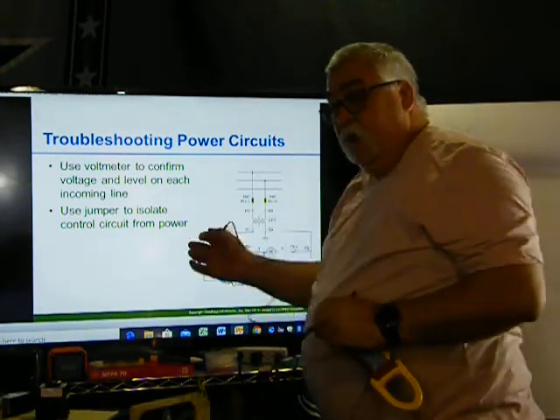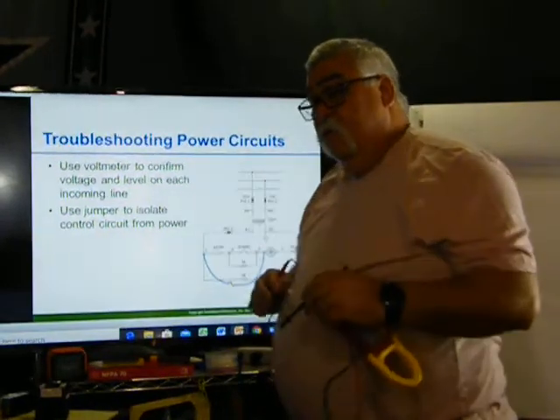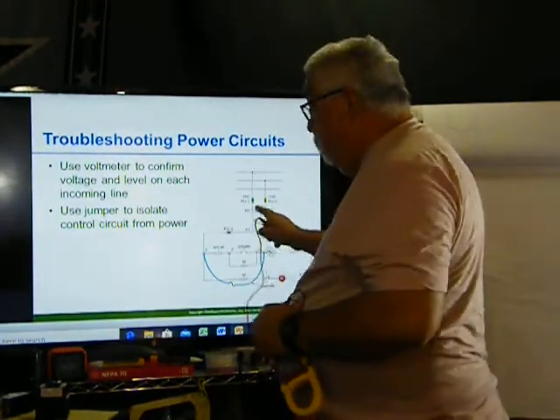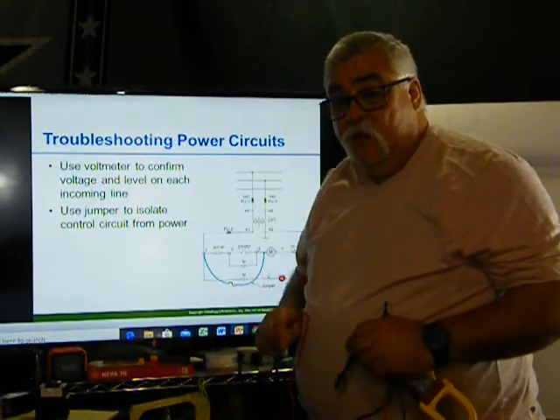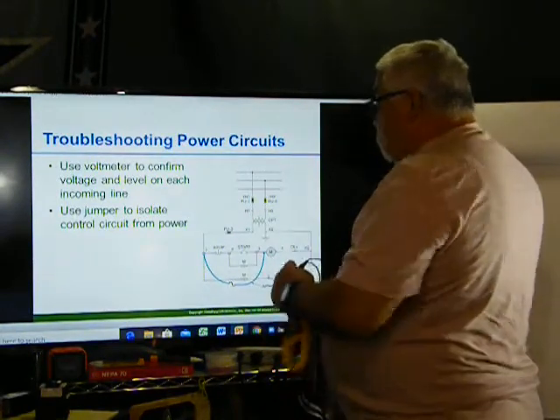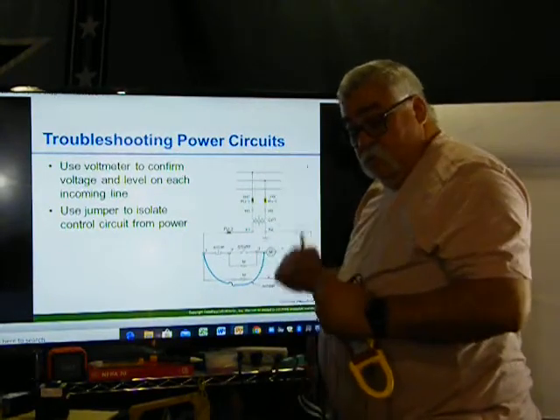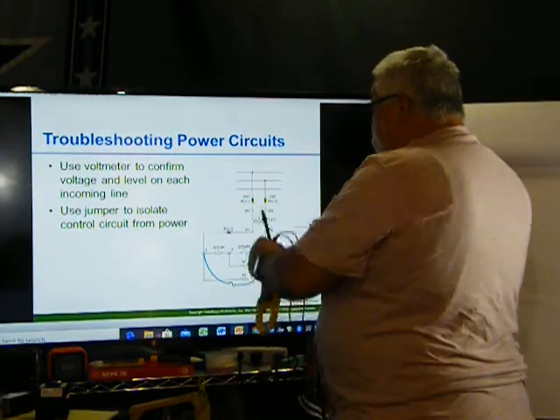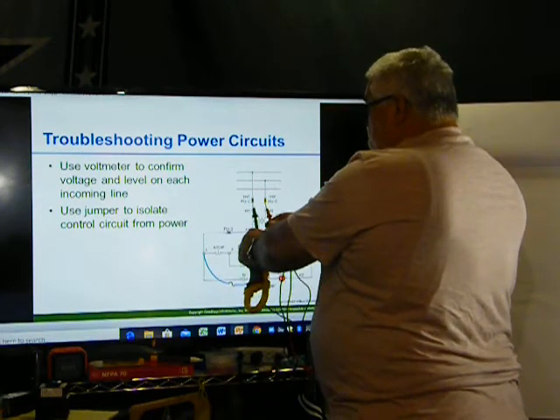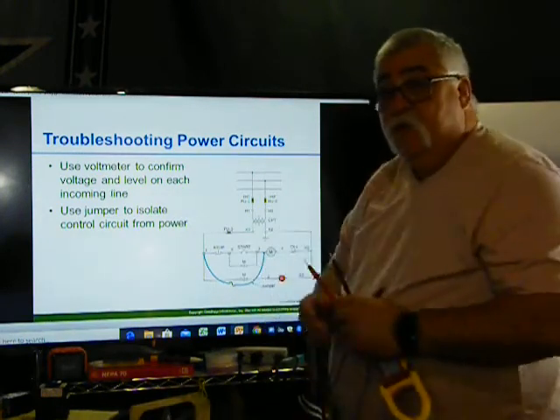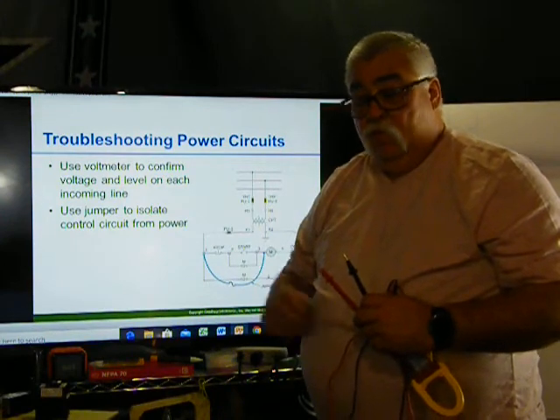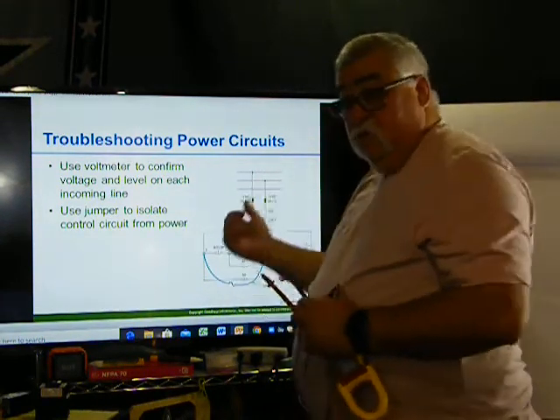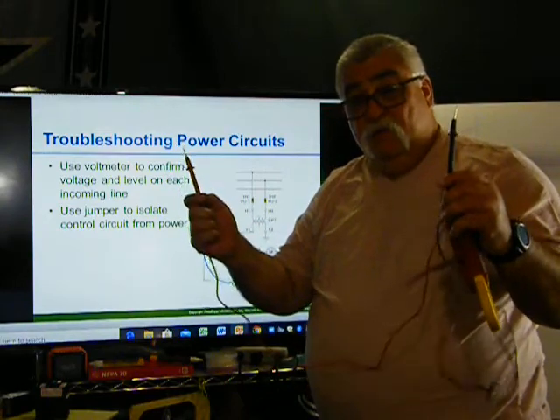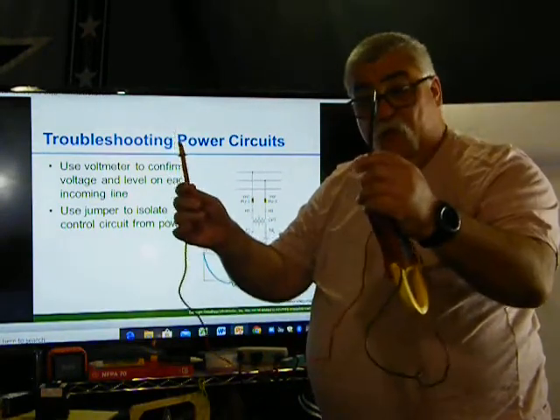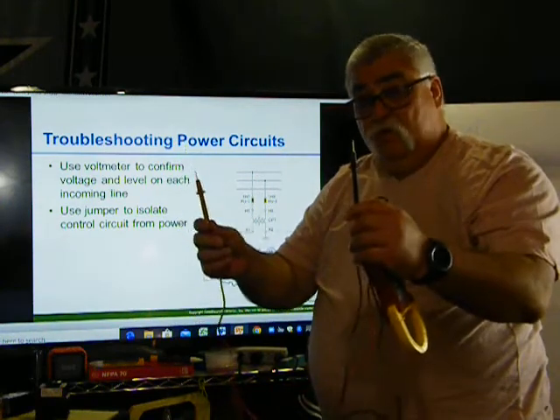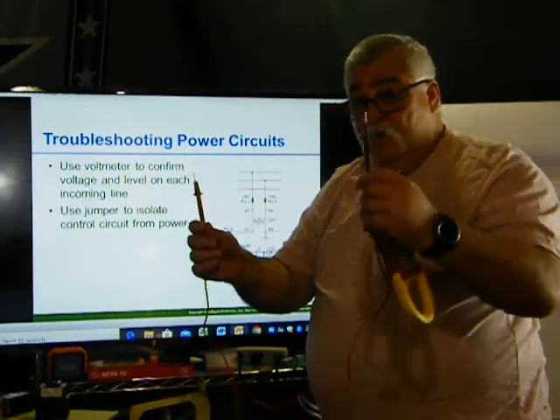Okay, so if I've got my 480 and 240 volts at each one, that tells me that power is present at the disconnect. Okay, now with the disconnect on, I can check across here. Let's say I don't have nothing. That tells me that one of those fuses isn't working. Why? Because I need two wires. In order for this thing to work, I've got to have two connections. So if I'm going across two hots and one hot's not working, guess what? It's not going to give me anything.